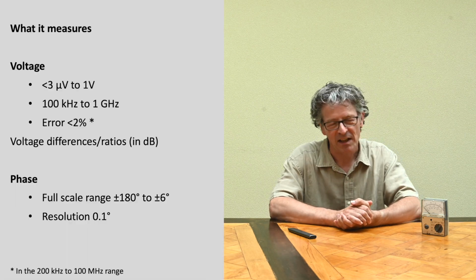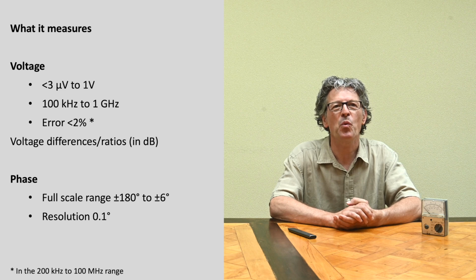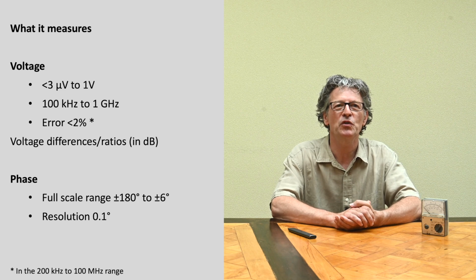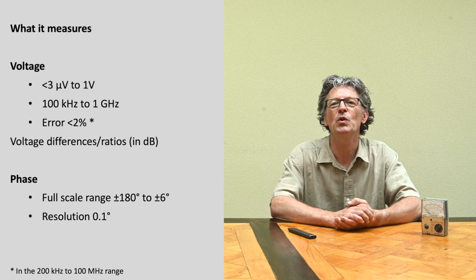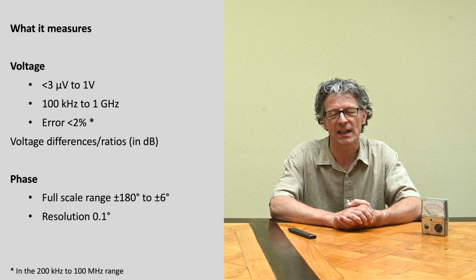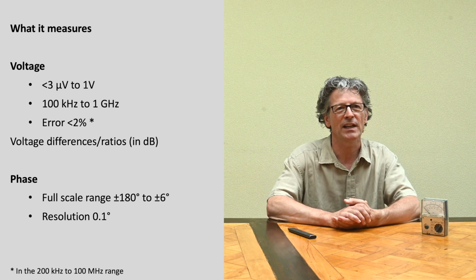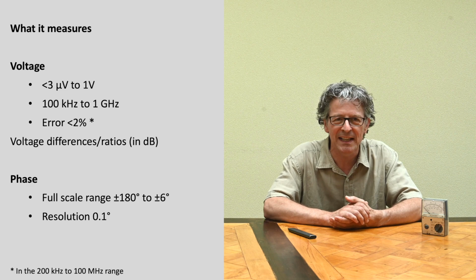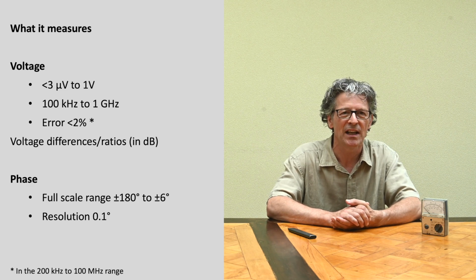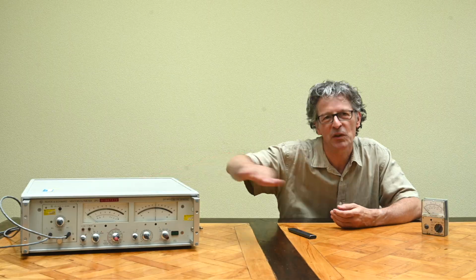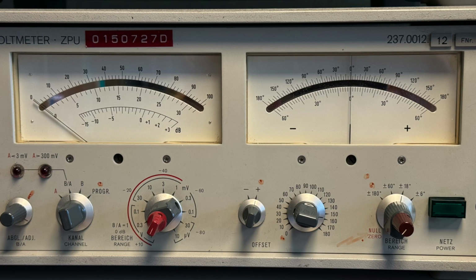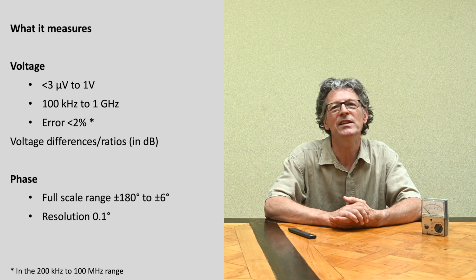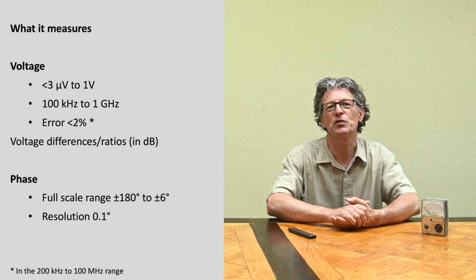Now, first of all, the basic characteristics. It's a device that measures voltages and phase. Voltages, it can measure quite small amounts of voltage. It allows you to measure from less than 3 microvolts up to 1 volt, and with a divider up to 100 volts. It was originally with the unit, but I don't have that divider. We can measure those things all the way up to 1 gigahertz, and the measurement error is relatively small at 2%, though that depends on the frequency range you're measuring in. And given that we have 2 beautiful analog meters here, it's probably not getting any closer. We can also do some ratio measurements between channels. I'll get to that when I do my measurement test here.